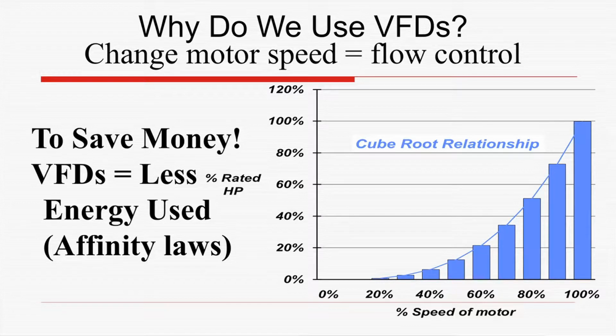So how do we save the money on a VFD? Essentially, this is mostly related to HVAC applications. This is fans and pumps. There's a mechanical law about how fans and pumps operate. It's called the affinity laws or the fan laws. It relates to how power is consumed using a fan or a pump, and it's not a linear relationship. If you notice, this curve goes up pretty fast with the speed of the motor, and that's equal to the flow. So how fast you're getting flow of the pump or of the fan, and the energy you consume. So 100% speed, 100% flow gets you 100% of the horsepower. All right, pretty straightforward. But if you can reduce the speed just a little bit, you see that the energy just drops off a lot faster than linear.